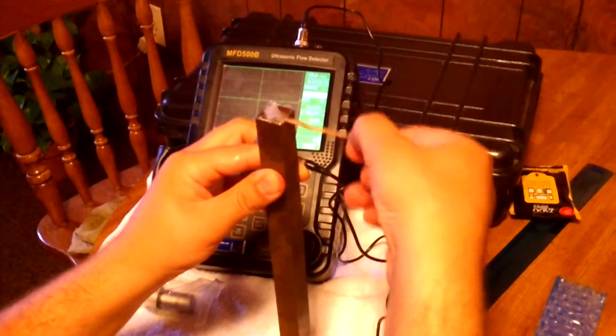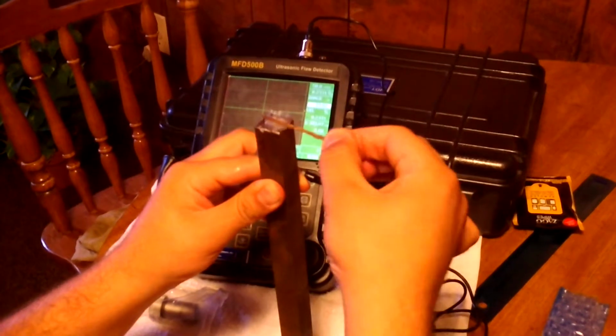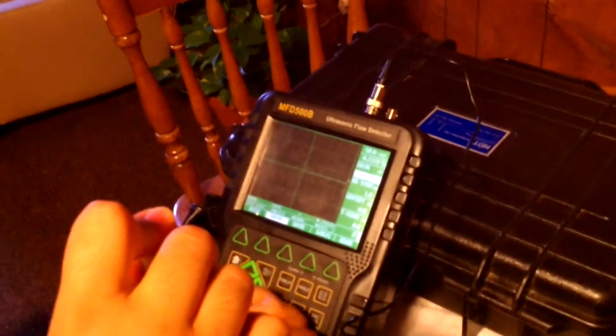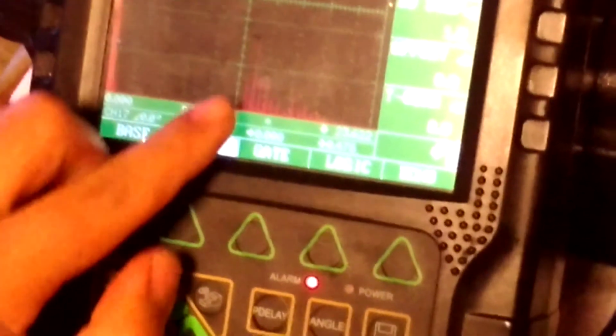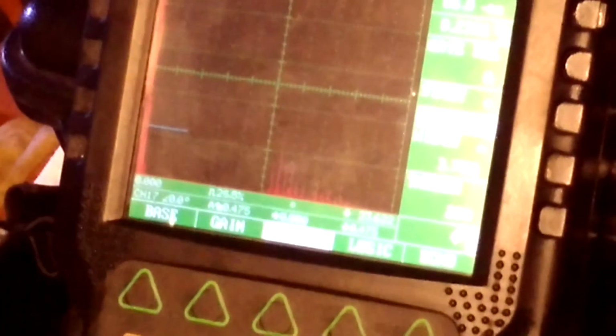I put a couplant material, and this material will prevent any air gaps between the probe and the bar. Now I increase the gain, and as you can see, I increase the gain looking for this peak, this peak I'm looking for. If I choose a gate, and this is the gate, I change its position until the gate hits the first echo.